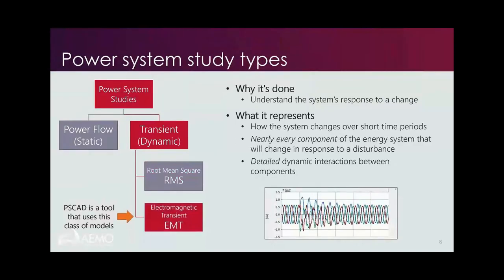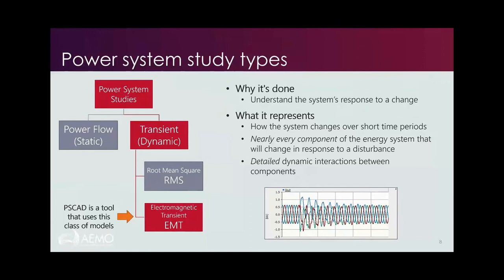Extending from RMS is EMT — electromagnetic transient simulations. It does the same thing as RMS: looking at how the system responds to a disturbance over short periods, except in far greater detail. The tool we use, PSCAD, essentially means we have no limits on what we simulate. We can model transients, full transmission line models, detailed transformer models, DC, and as much detail as we want. We can model nearly every component that changes in response to a disturbance and study detailed dynamic interactions between components. The downside is that it is computationally slow compared to RMS type studies.